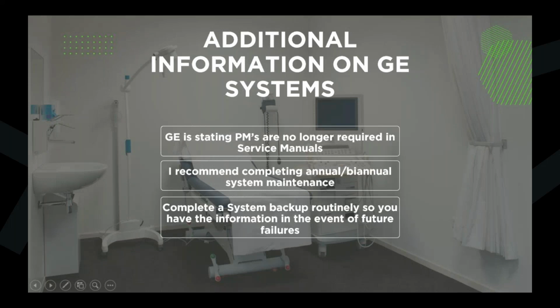All right, some additional information on GE systems that I like to include here is that on all of their newer systems, it's saying PMs are no longer required in the service manuals. So I know a lot of departments have gone to the point where they say don't even put them on a PM schedule. I would advise against that, and I would still recommend at least completing an annual system maintenance on it. At the very least, you can go in there, back it up, and take a look at the transducers. I still want to make sure I'm completing the system backup routinely to have that information in the event of failures.